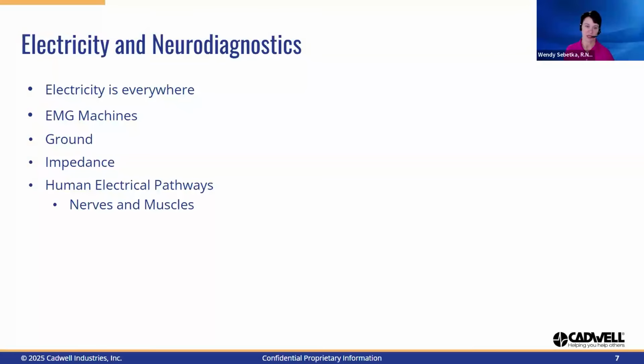The EMG machine uses an alternating current source to generate a direct current stimulus. The stimulus is applied through 2 poles, a negative or cathode pole, a positive or anode pole. The stimulus evokes a response which is filtered through a differential amplifier that measures the potential difference between the negative and positive inputs. We refer to these negative and positive inputs as our active and reference electrodes.